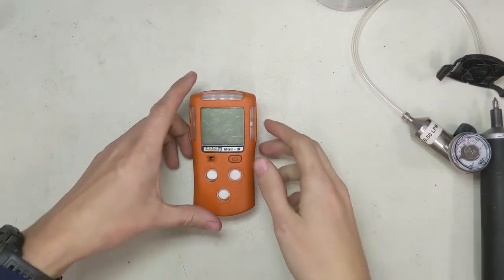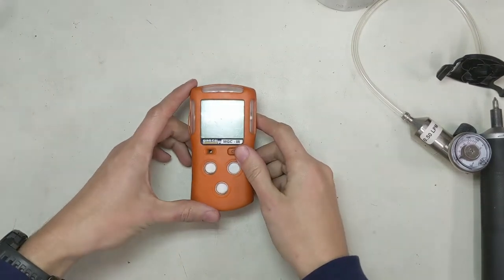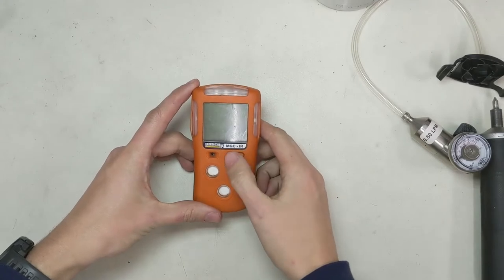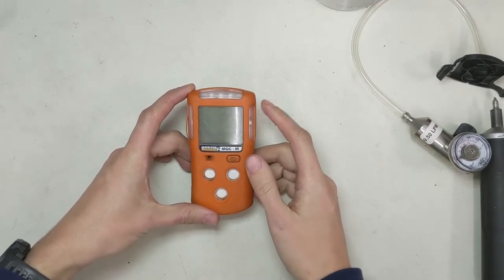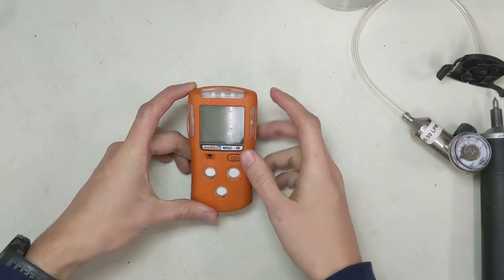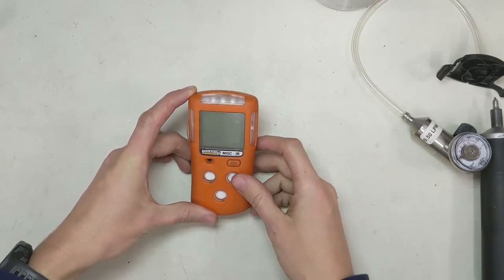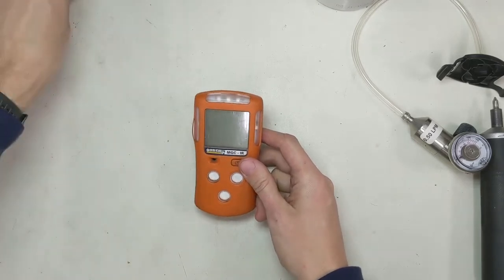Hey, I'm James Moore and welcome to the Ideal Calibrations How to Repair Your Gas Detector Series. Today we're going to look at the MGC IR, the Multi Gas Clip IR, and this unit's got a bad oxygen sensor in it. It's freezing at 20.9 and it won't go below. So I'm going to show you how to open it up and swap the sensor.